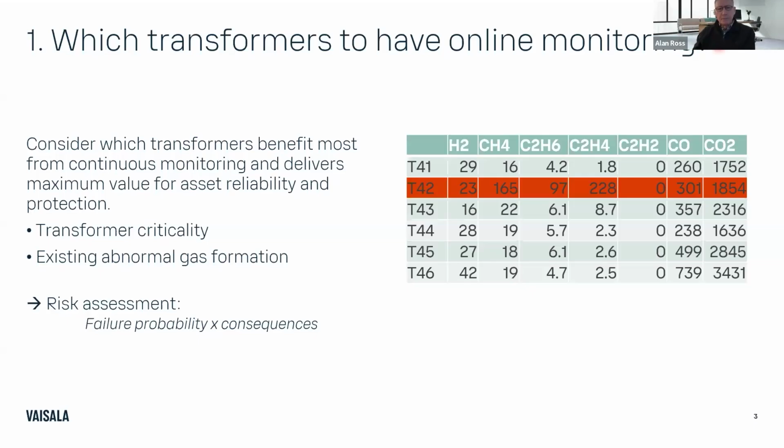The other one is multi-gas versus single gas. If you did hydrogen, it's my understanding that hydrogen is the first gas to show up, but it's also the first one to dissipate, so you can't really rely on it. But if you put a check engine light, a hydrogen monitor with maybe temperature or something else, pretty inexpensive, you can put more of them on there.